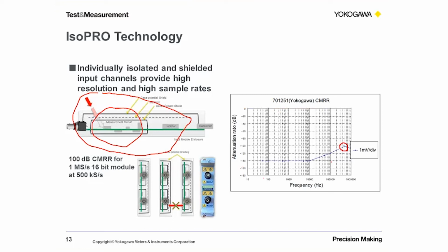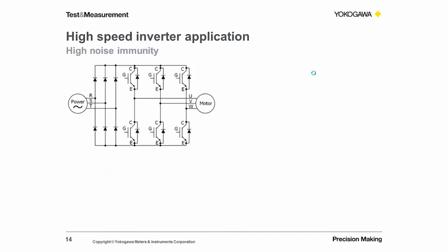means in practice, of course, is if you are looking at control signals. This is an example: we're looking at a control signal within an inverter. You've got potentially high voltages on the motor side, on the output of the motor, but we've got lower signal voltages, and we want to look at the gate signals as well.